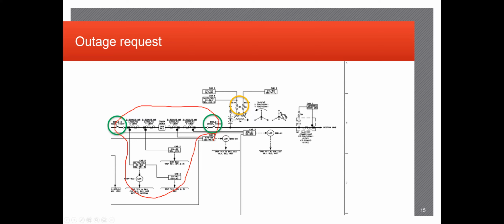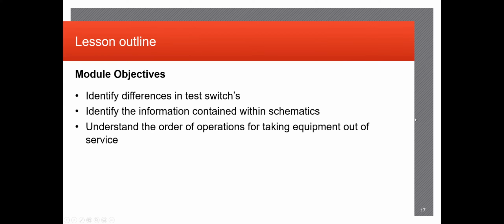This circle here also is primary fuses coming off this station service to pretty much show that this is how the relays are powered up, and identifying the correct circuit breakers in the control house to isolate those as well is important, because you don't want DC power on while the electricians are in there, because that can lead to, again, injuries, dangerous stuff. So going over some schematic review, test switch operations, this is going to get into the isolation portion specifically quite a bit. So identifying differences in test switches, information contained within schematics, and understanding the order of operations for taking the equipment out of service.